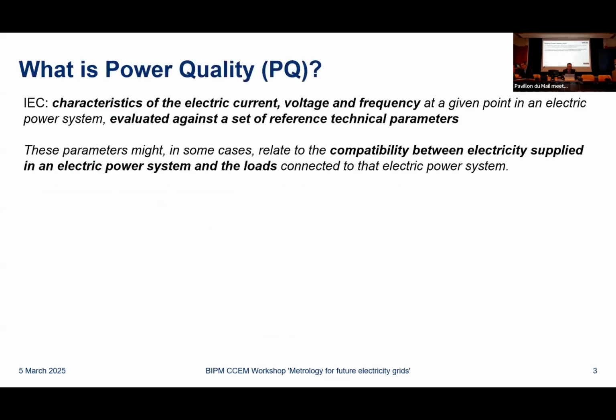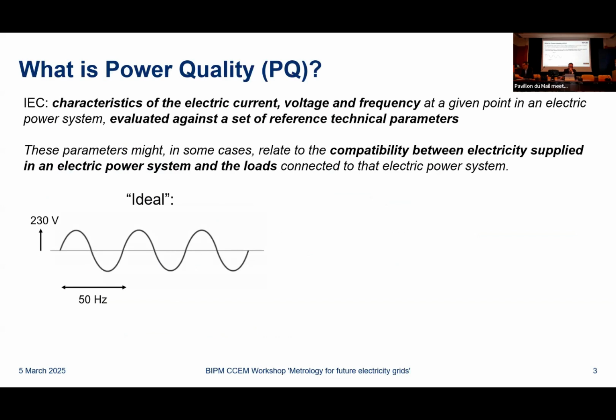So firstly, what is power quality? Well, if we go to the IEC vocabulary, it tells you that it's the characteristics of the electric current, voltage, and frequency. And we try to keep them within certain reference parameters. It's also very much related to making sure that the power being produced is compatible with what the loads would like to consume in order to function properly. So in an ideal world, this is what power should look like. You've got, for example, a very sinusoidal 230 volt waveform, 50 hertz frequency, which in Europe is the reference, or in other places 60 hertz.